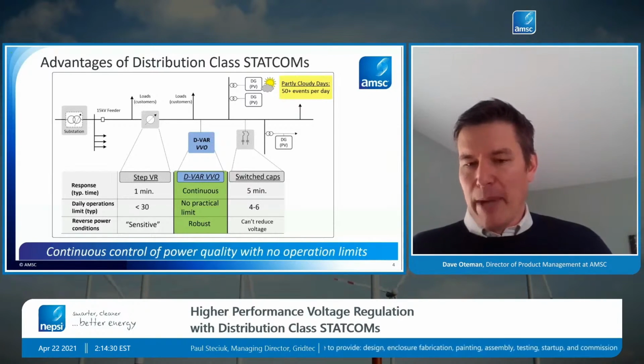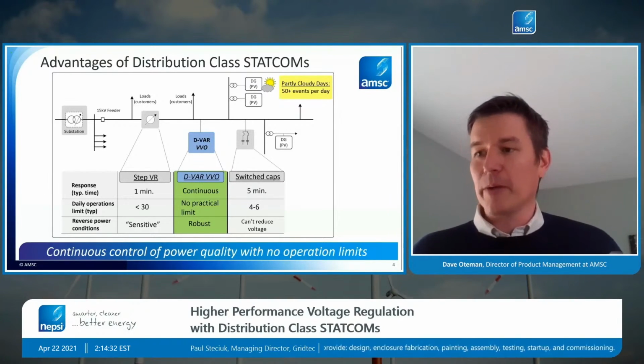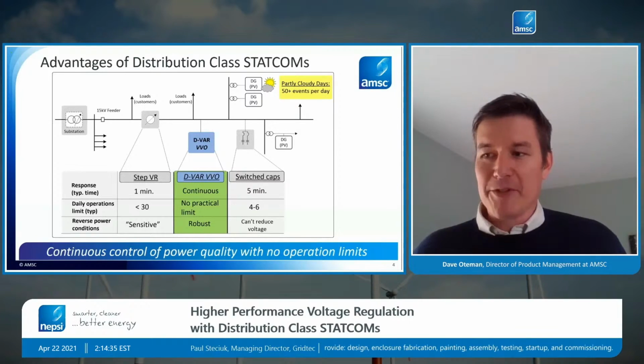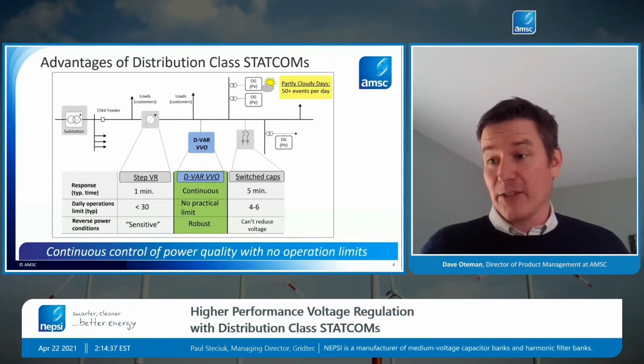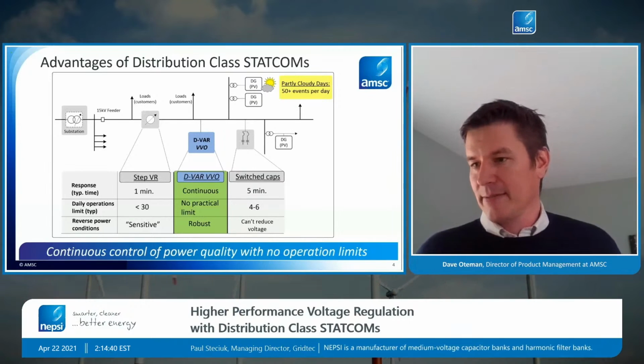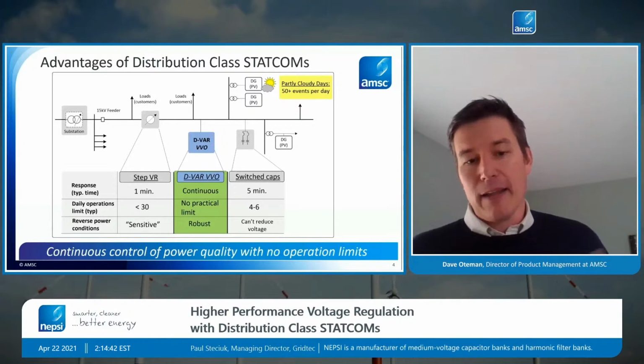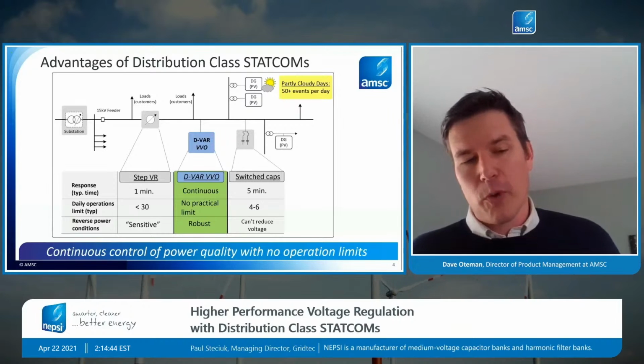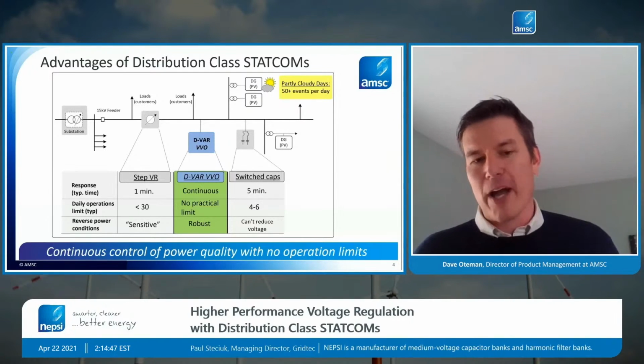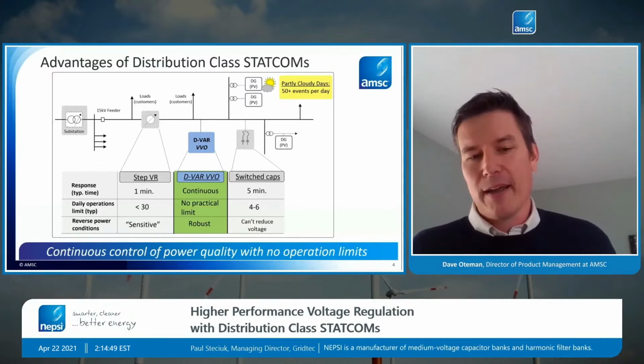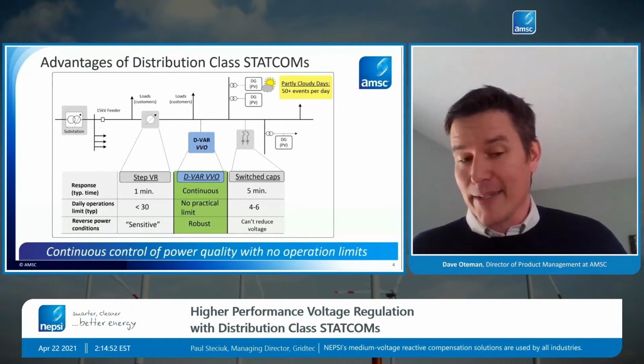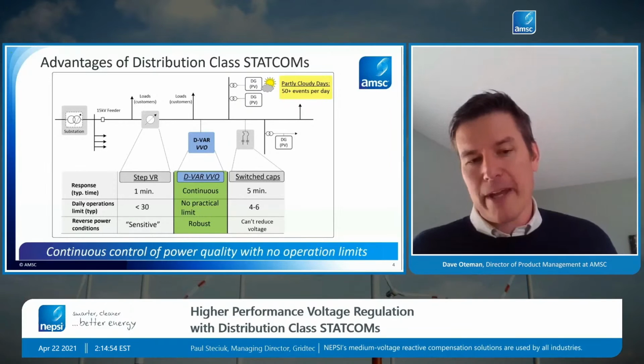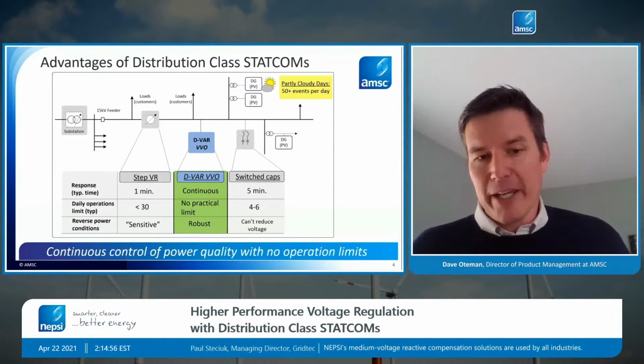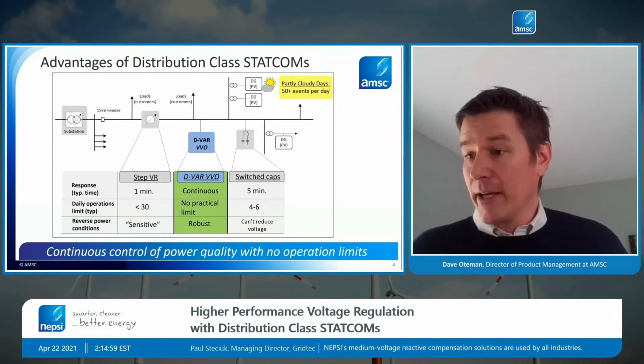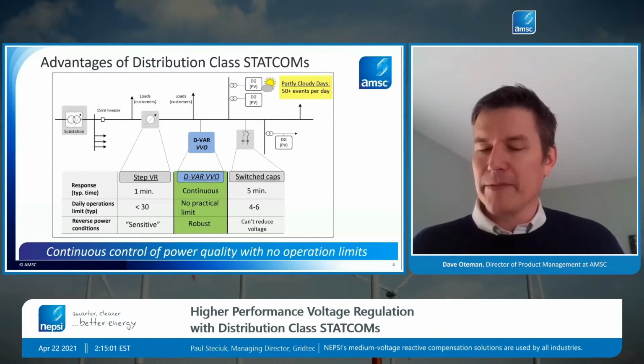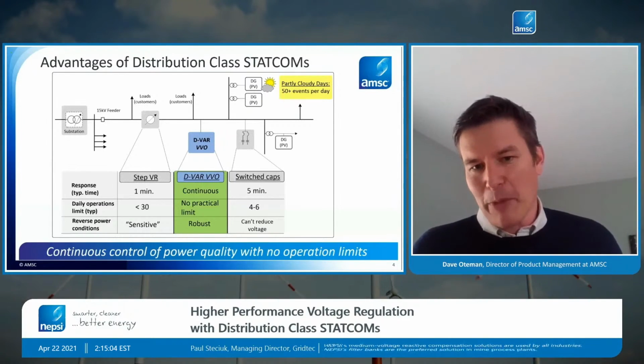And then of course a capacitor bank cannot pull the voltage down, it can only boost the voltage up. When we have generation causing reverse power flow, we actually need to pull the voltage down, so the cap bank's not going to help us there. Line regulators really are also quite limited in terms of their operation. If we're trying to compensate for over 50 events a day, and both the ramping up and down of that, line regulators are also not adequate to solve that problem, and they're not reliable enough to solve that problem. And we'll talk a little more about that.